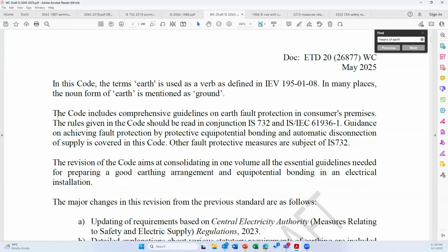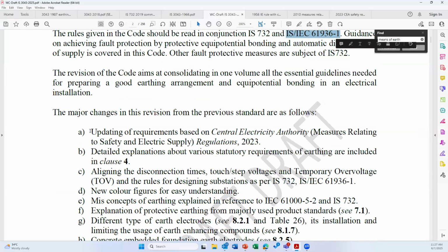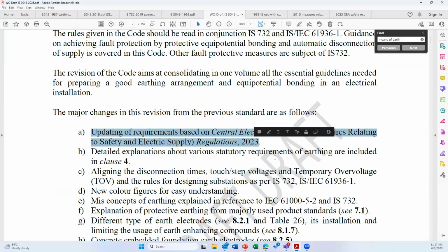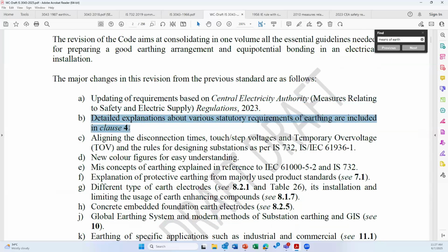As you can see here, the code includes comprehensive guidelines for earth fault protection in consumer premises. The rules given should be read in conjunction with IS 732 and IS IEC 61936. Here, IS 732 is for voltages up to 1000 volt AC, 1500 volt DC, and 61936 is for voltages beyond 1000 volt AC. Similarly, the code of practice has been updated based on the new definitions in the CEA regulation. In clause 4, a detailed explanation is given which talks about the statutory requirements of earthing. Statutory means the legal requirements of earthing.